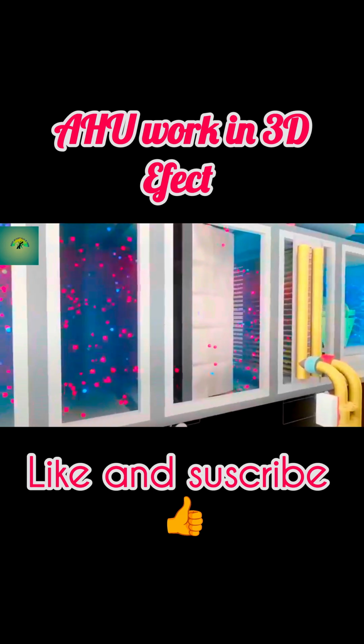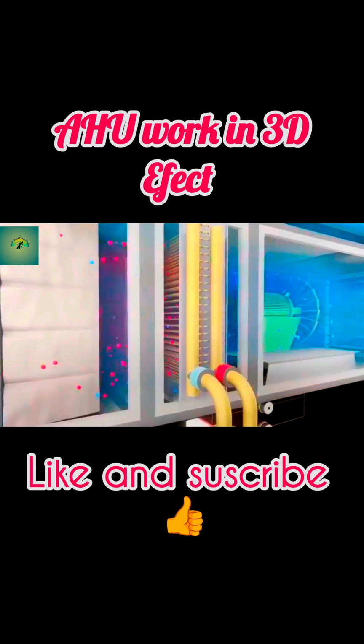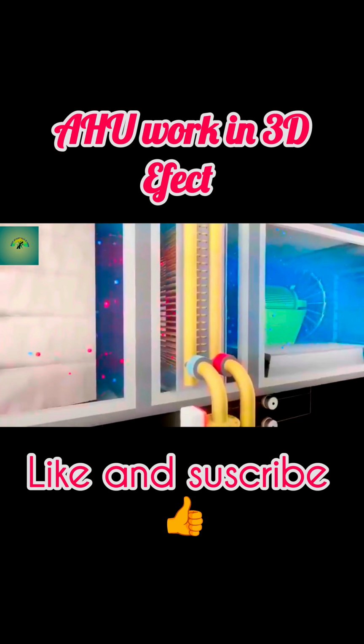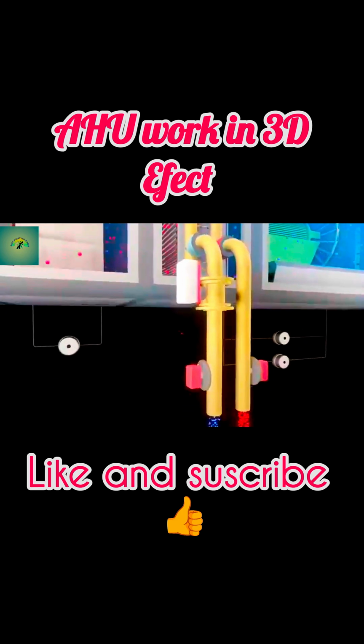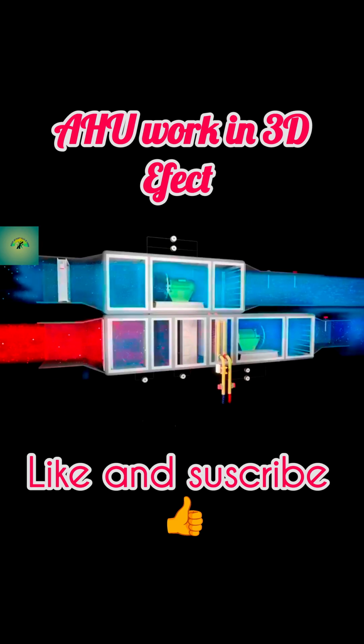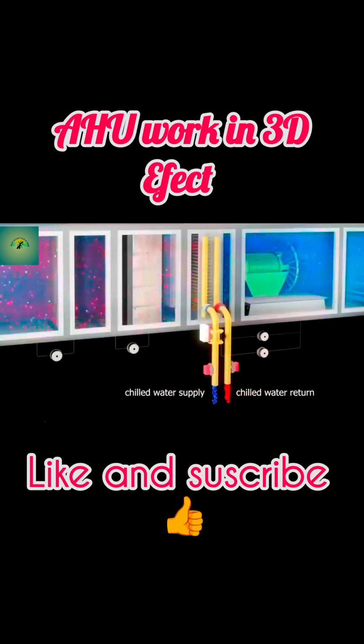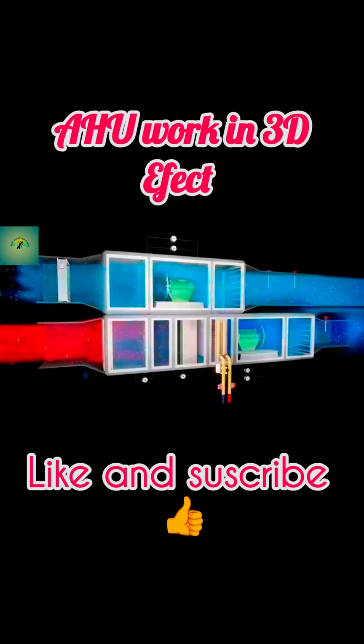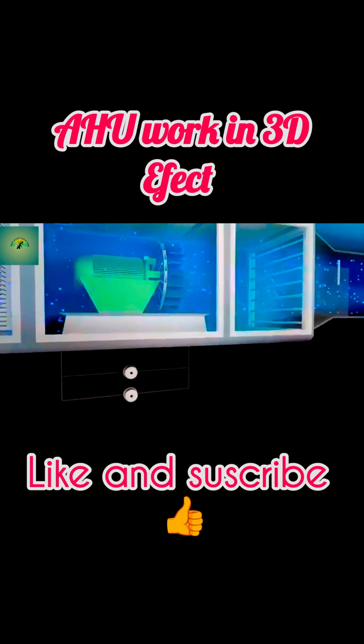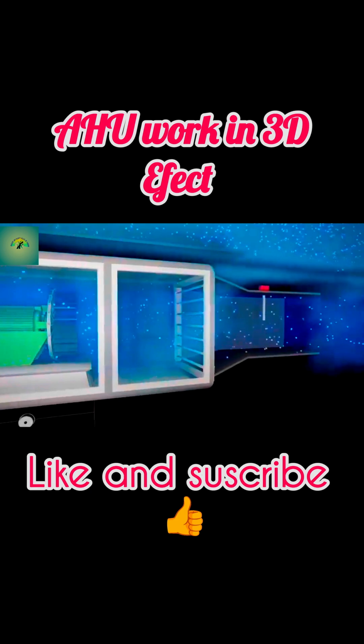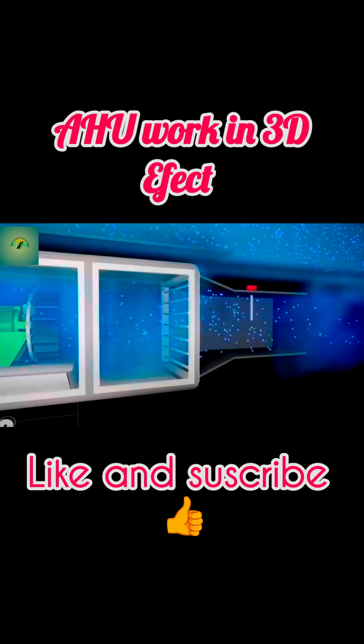Next, the air passes through the heat-exchanging coil. The heat exchanger cools or heats the air in the process, depending on the type of air handler. Hydronic air handling units have water that flows through the coil. The water can either be hot or cold depending on if the air handler is heating or cooling a space. As the water flows through, the coil changes temperature. The fan blows air over the coil, and the air is heated or cooled by the coil.